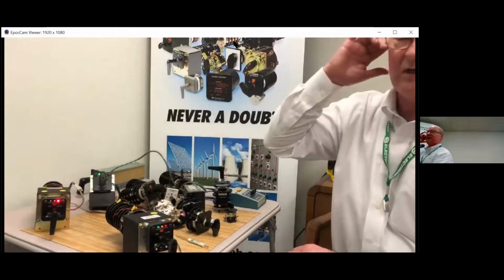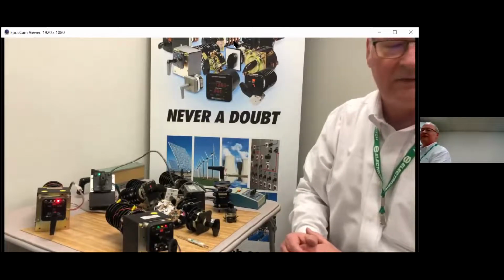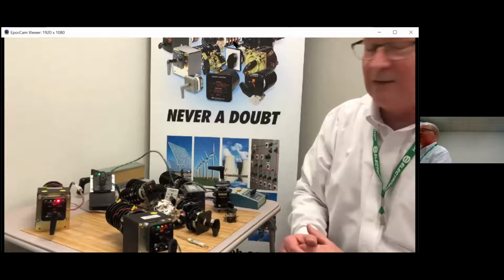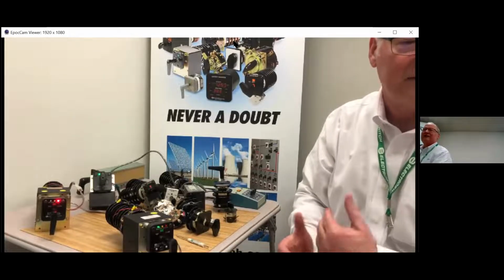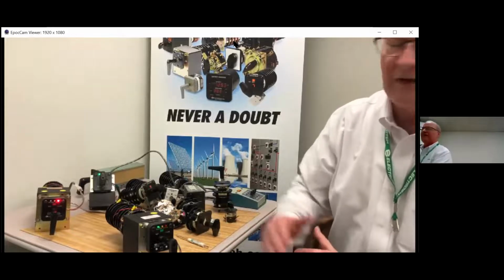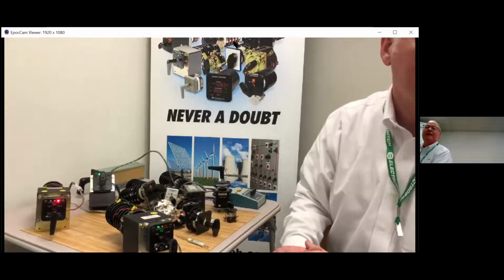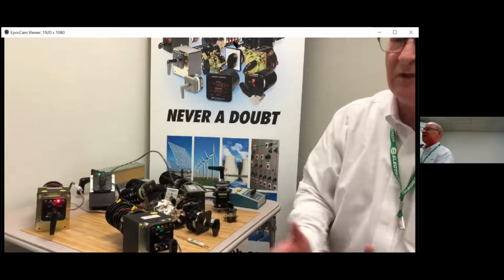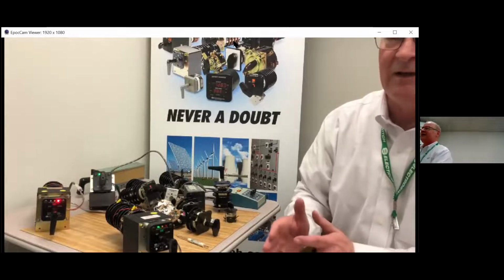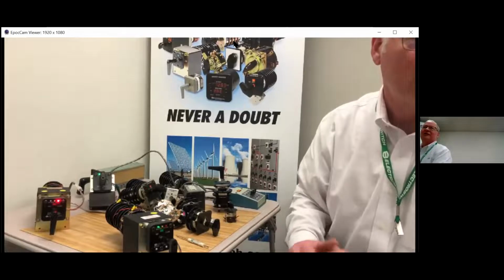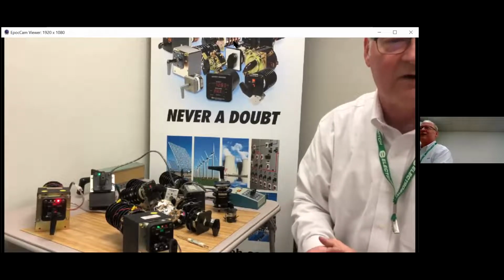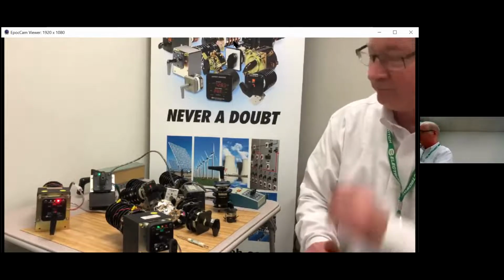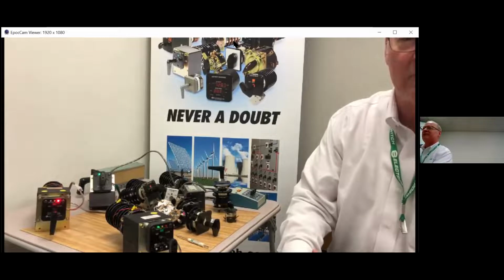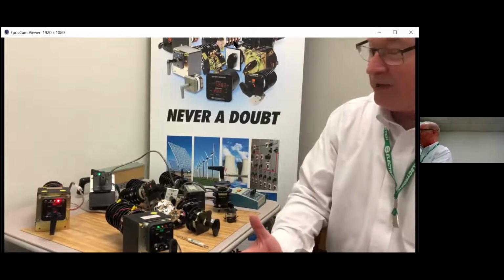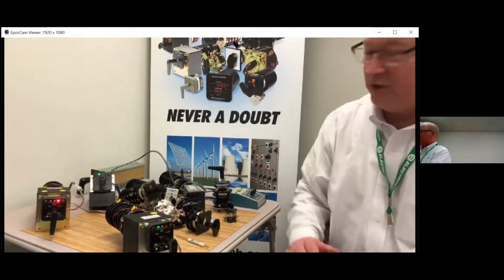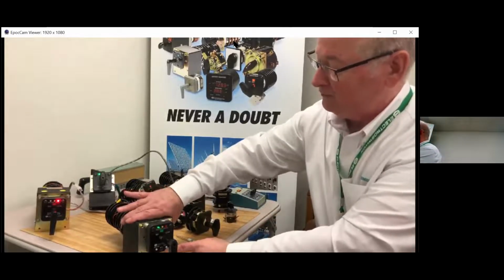Once I release the button, it's going to time out 7 seconds and then get a little faster after that, but it's going to give me time to leave the space and have the switch operate. Hopefully everybody noticed that did operate. Now this particular switch comes in different time versions of 10, 20, 30 on up to 90 seconds for whatever a customer feels is the desirable safe time for them to leave the room and come back in. So if they're doing maintenance on a breaker, they can go in, maintain the breaker, and then when they're done, they can do the reverse function with the delay close button.